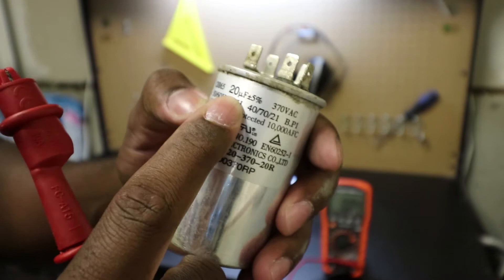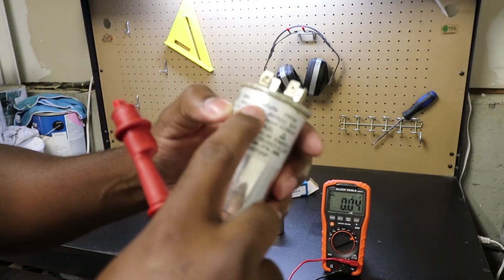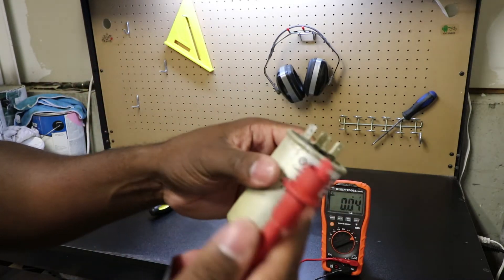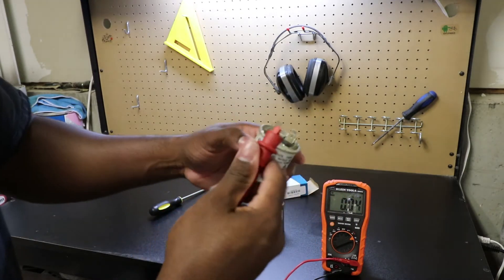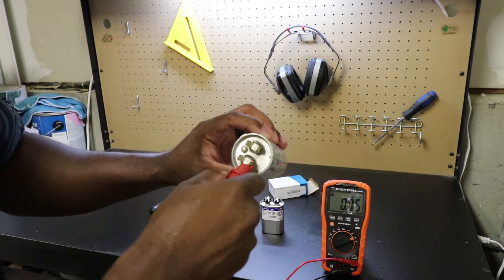This is 20 microfarads, plus 5%. That means this needs to be 20 microfarads, or maybe 5% more, probably maybe 5% less, and it's still good. So let's test this one and see what we got. I'm going to put a lead on here.